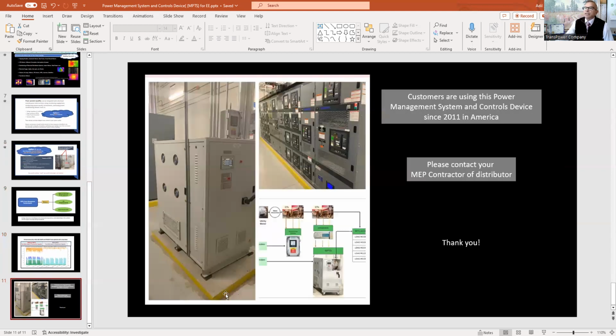So let's summarize it. It looks like this, sitting in an electrical room connected to the switchgear, the main bus bar. Here are the connections—very simple. You have CTs to measure close to the meter, so you have the utility meter and another meter comparing what's happening. That's the power management system. And then you have a dual power management system, because the MPTS also has a built-in power management system, so now you've got two sets of data showing what's happening in your network.